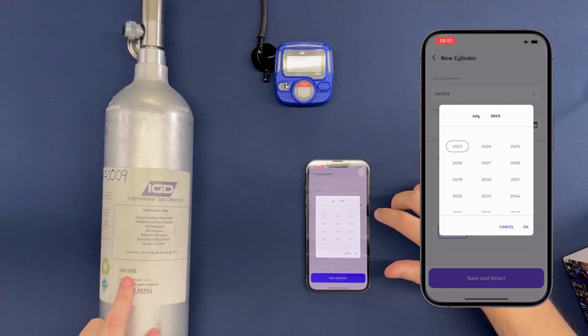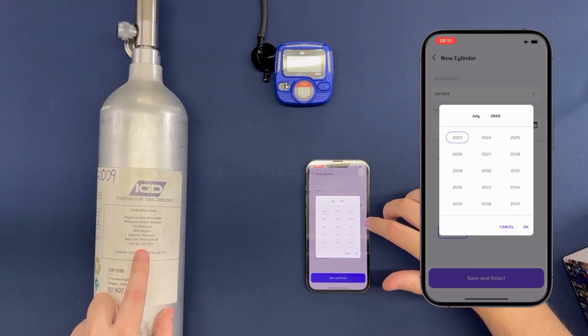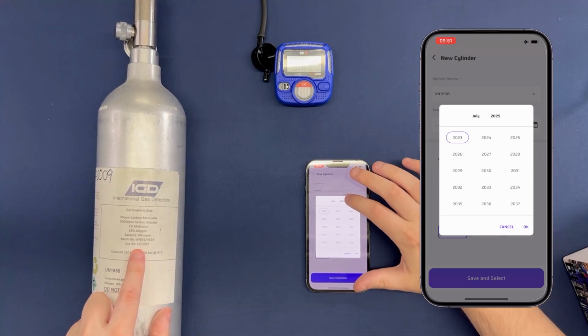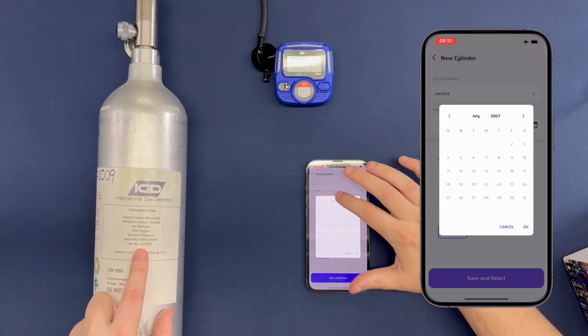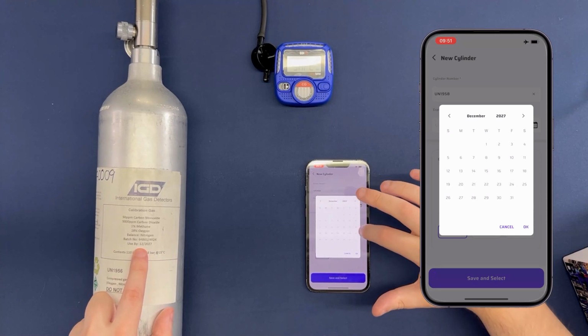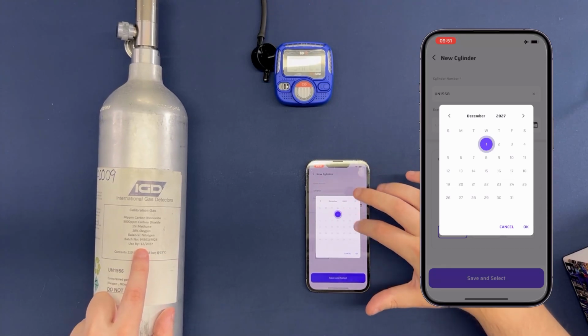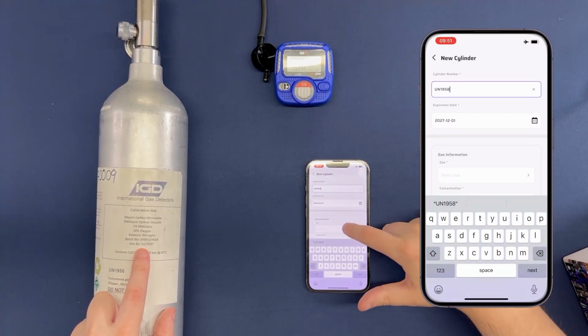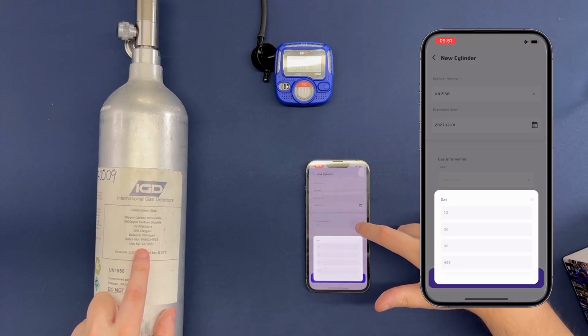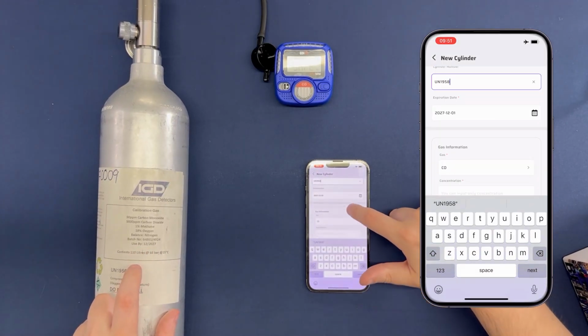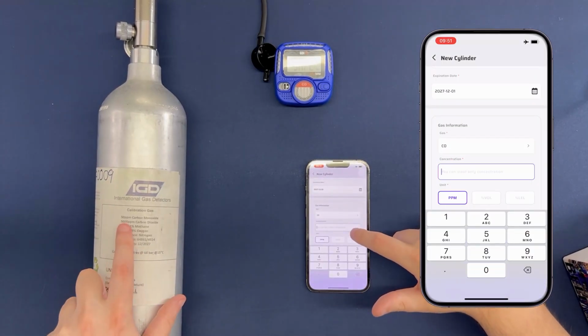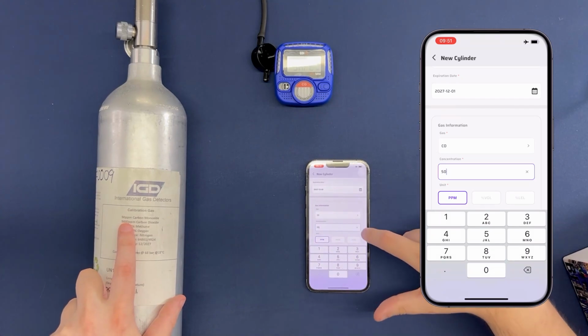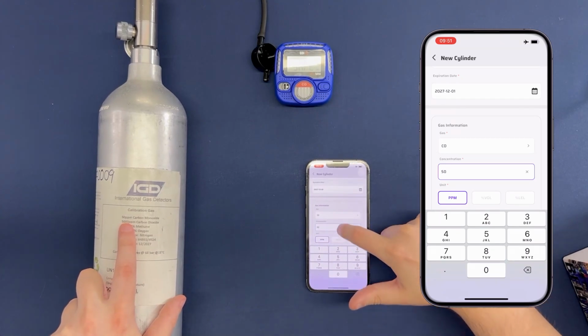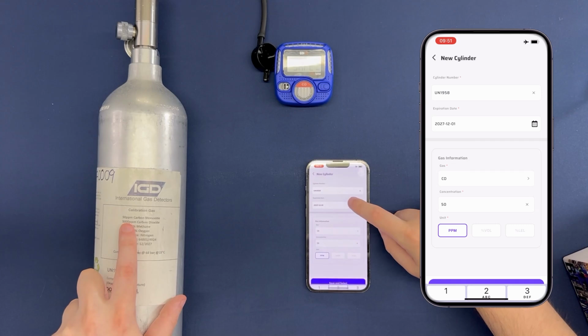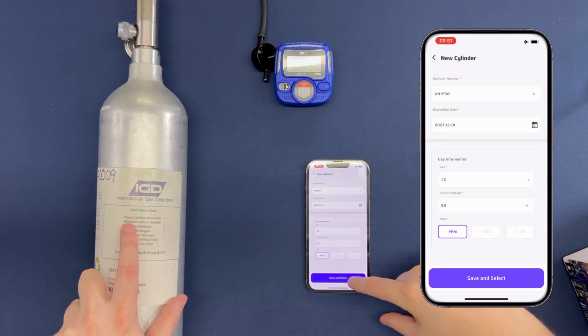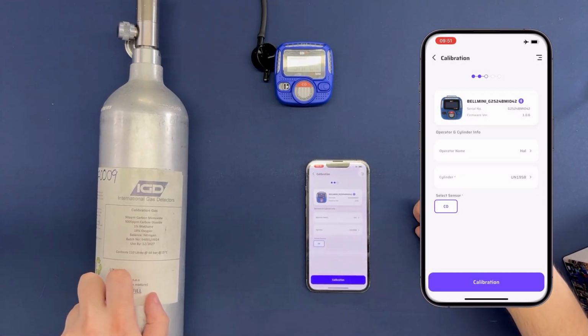It will ask for the expiry date. So this on here says used by 12/27. And then it will ask what gas information. So we've got CO, and the concentration, as you can see, is 50 ppm. And then I press save and select.